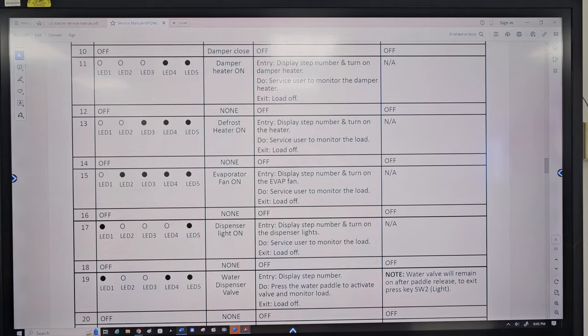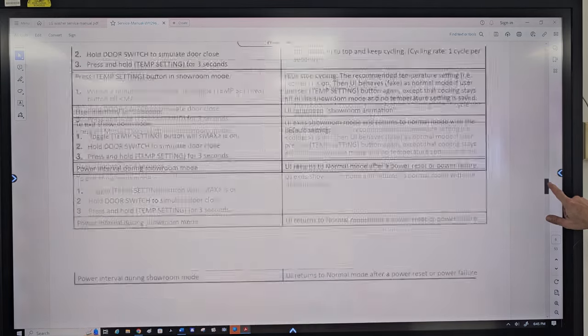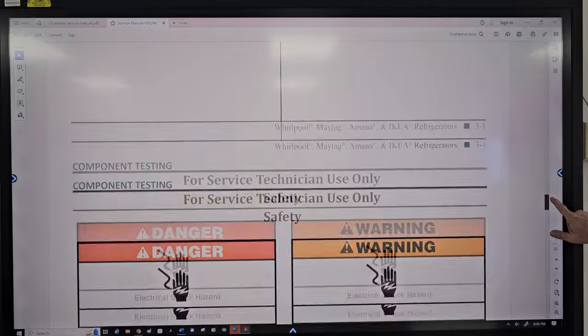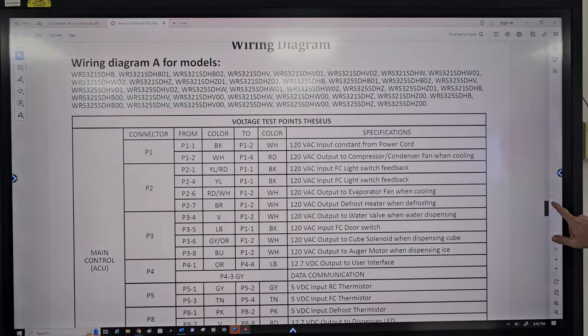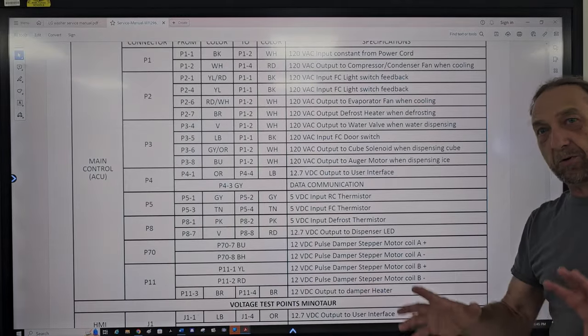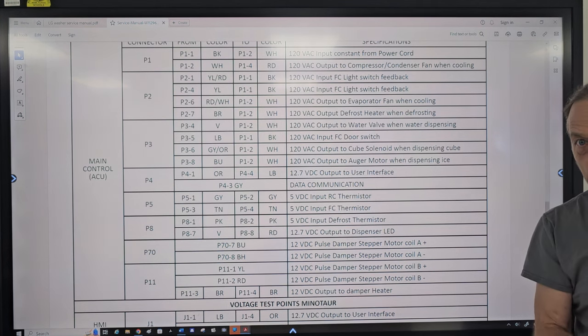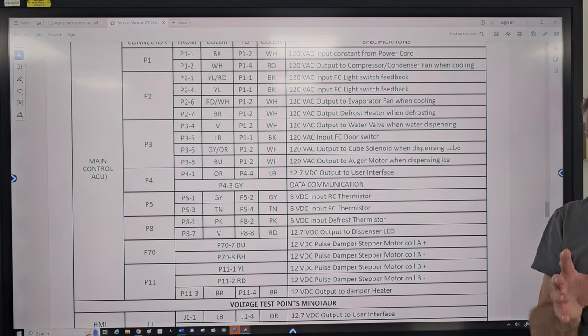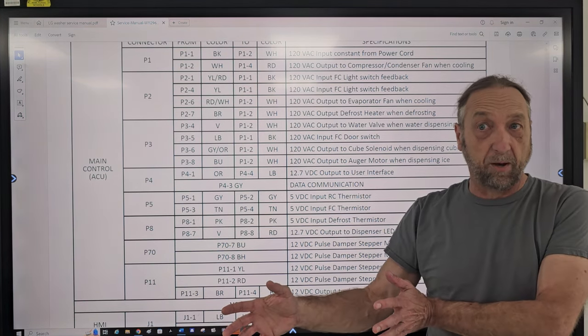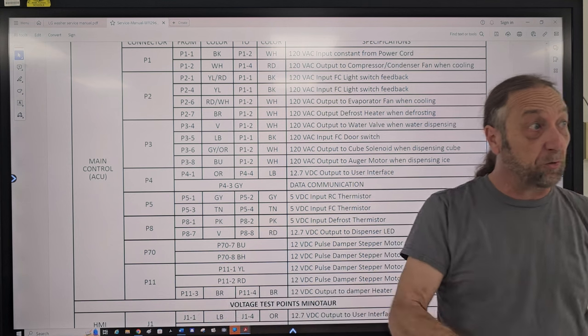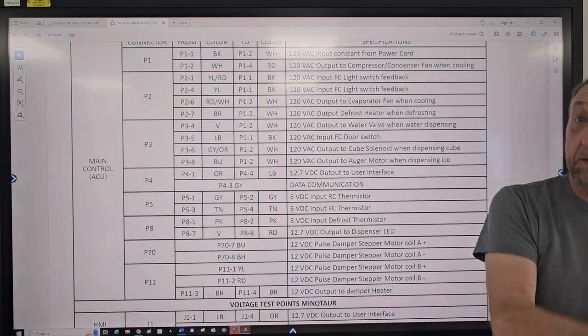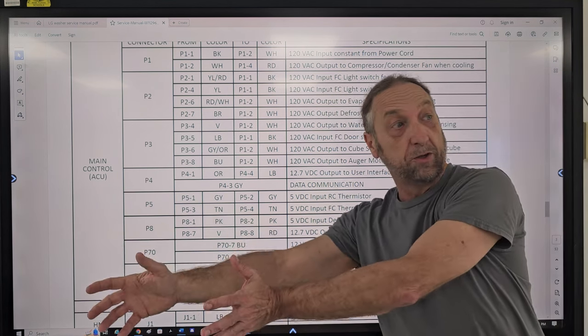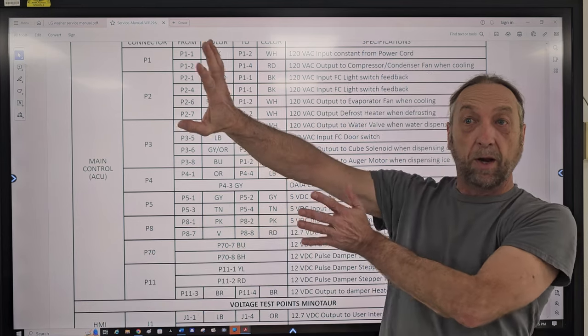Student: if the board is sending power to the damper and the damper isn't moving... Instructor: wait, we're talking about the fan motor, step 15. We said the damper cannot cause this problem - we're saying the freezer's not freezing, and the damper only controls air in the fridge, so we're not worried about the damper.